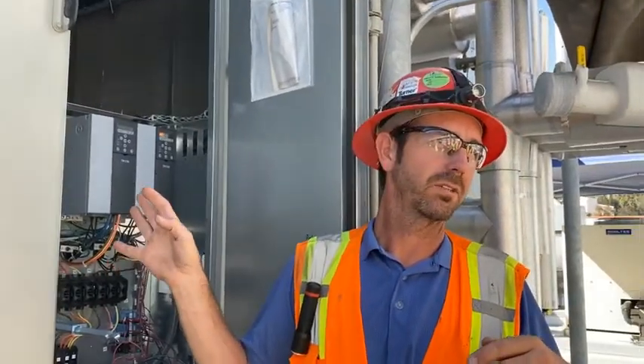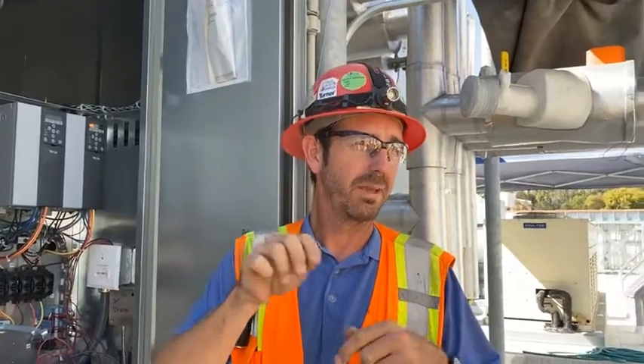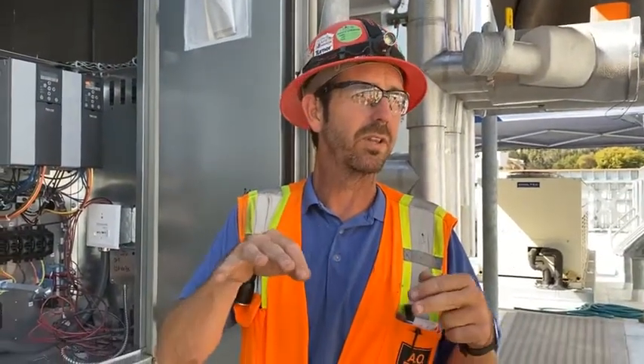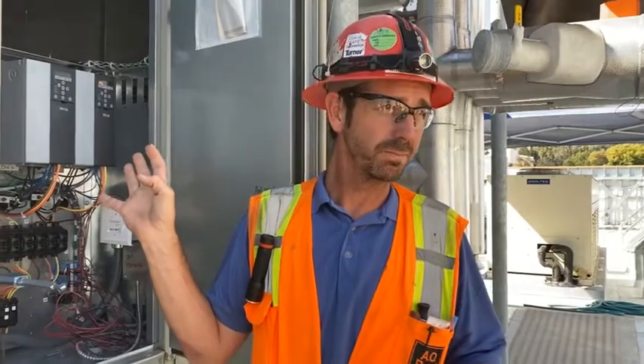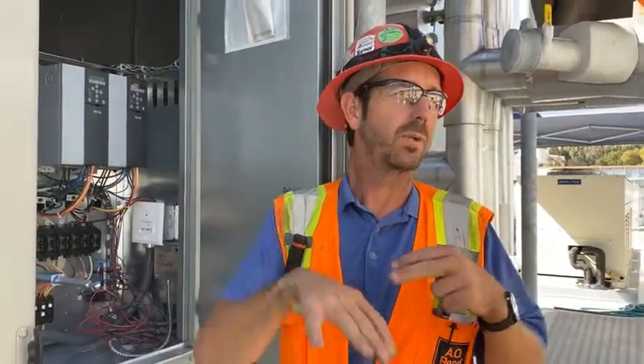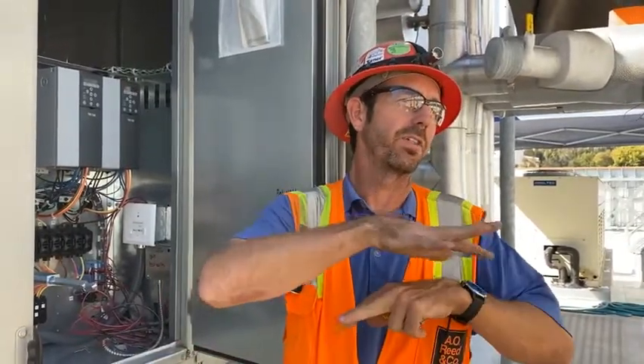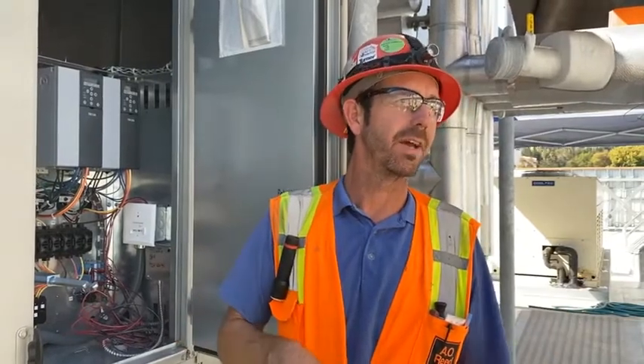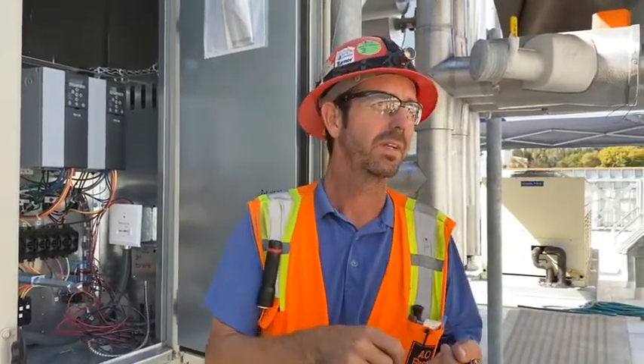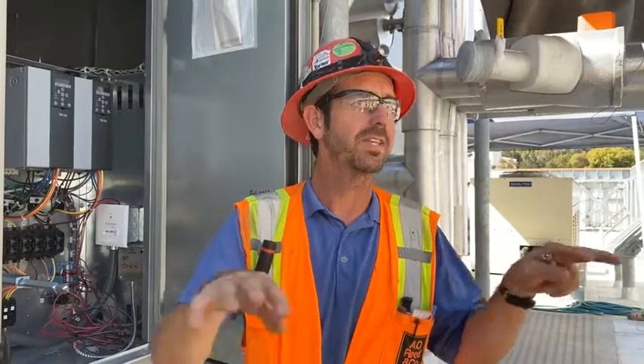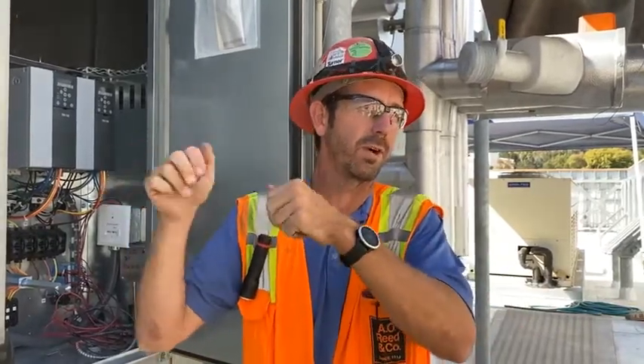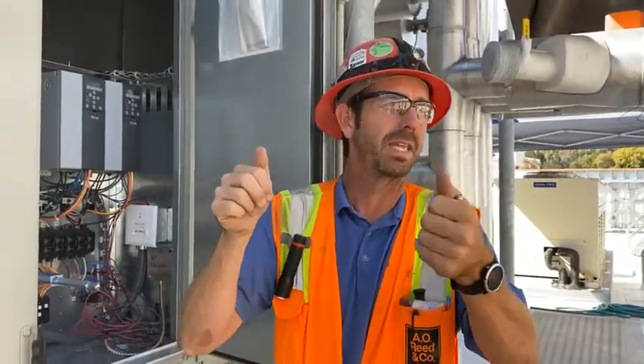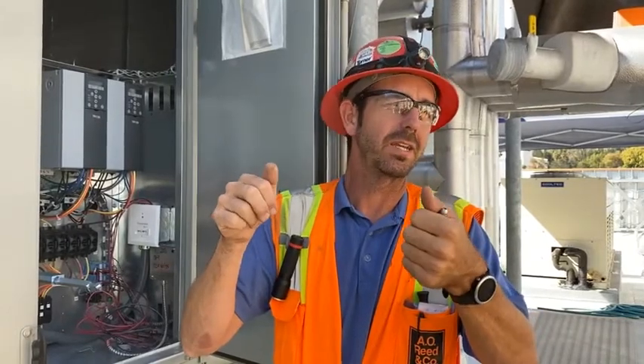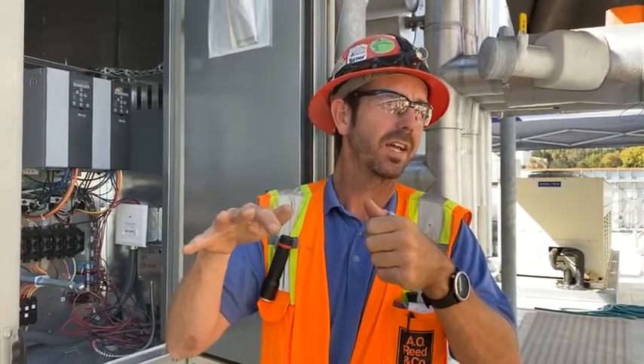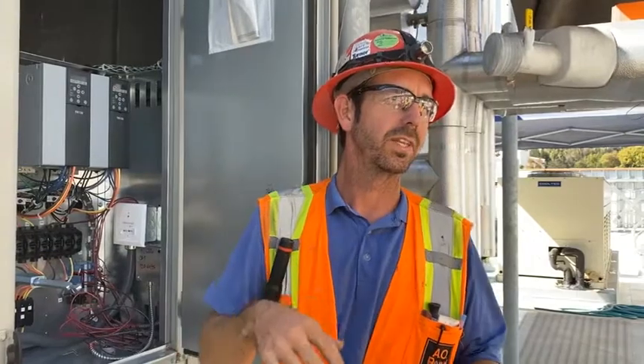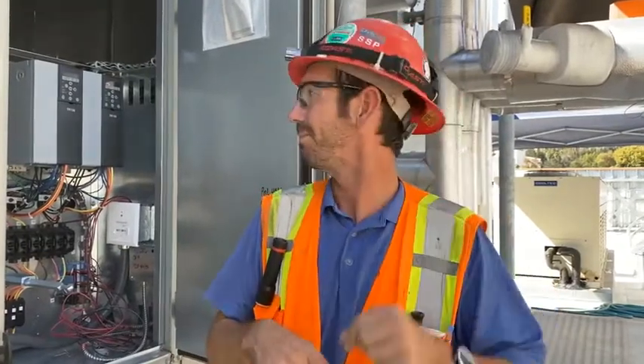run the unit. Sometimes they run it in hand, and they leave it in static pressure control, and they see what static the unit needs to run at with all those boxes open at their proper CFM. They write that number down. Each box is at its proper CFM because they've already calibrated each box. They know at full cooling that box is making the right amount of air. So then they see what static pressure is in the duct that they need to control to, and then they set that as their set point. Okay.